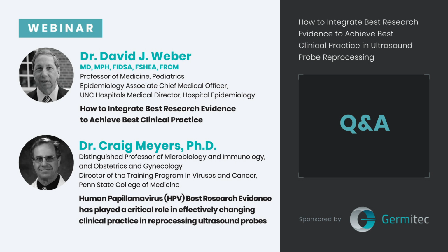And then you want to use recurrent pathogens that you would see in healthcare. So for what we're talking about, ultrasound probes, starting with vaginal and rectal ultrasound probes, you want things that would mimic, they don't have to be the exact organism, but would mimic syphilis and gonorrhea and chlamydia and other vegetative bacteria. You clearly want enveloped viruses that are herpes simplex or would mimic them, and non-enveloped viruses. And here, because they vary quite a bit, I think you would clearly want to show that the device or disinfectant was active against HPV. So you need to look at all of those factors in assessing whether the article is in fact valid.